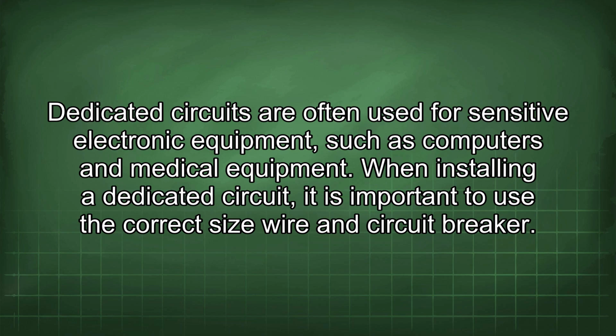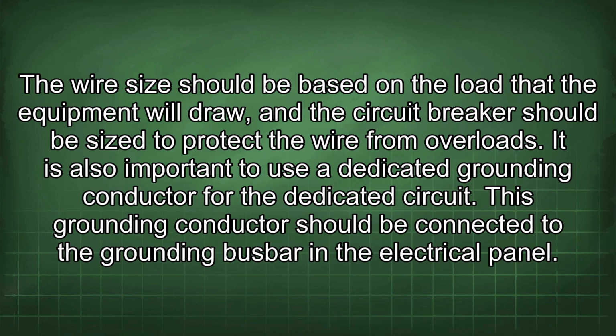When installing a dedicated circuit, it is important to use the correct size wire and circuit breaker. The wire size should be based on the load that the equipment will draw, and the circuit breaker should be sized to protect the wire from overloads. It is also important to use a dedicated grounding conductor for the dedicated circuit. This grounding conductor should be connected to the grounding busbar in the electrical panel.